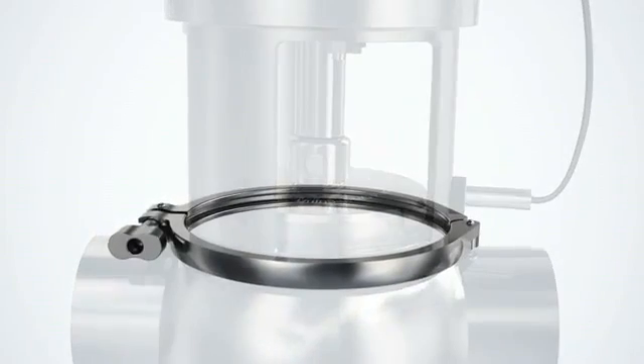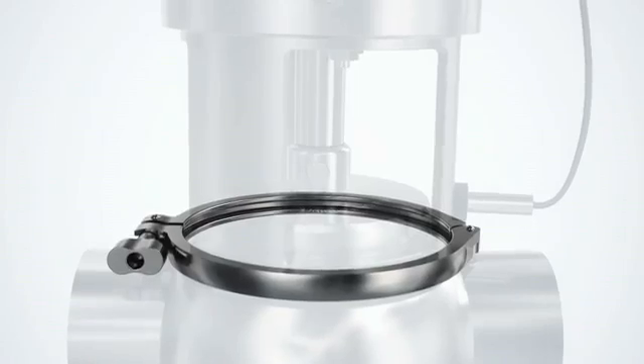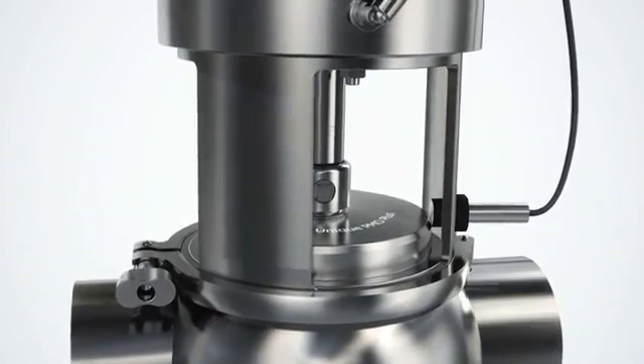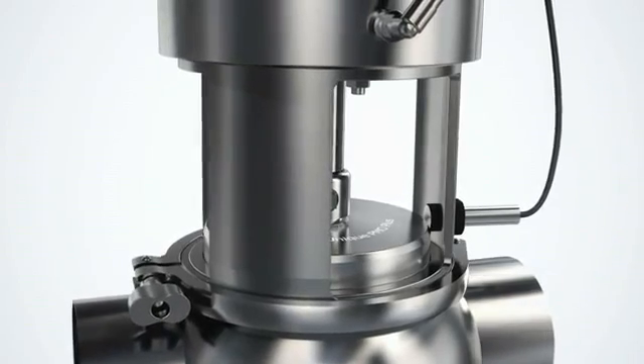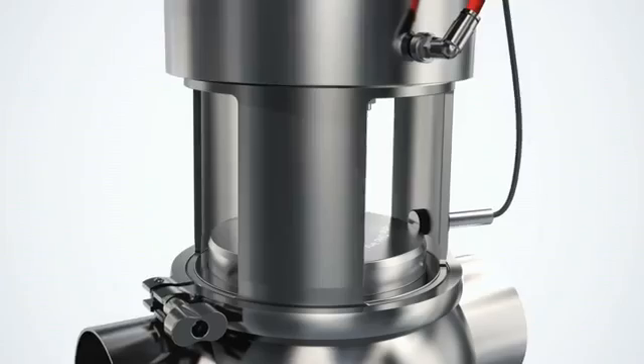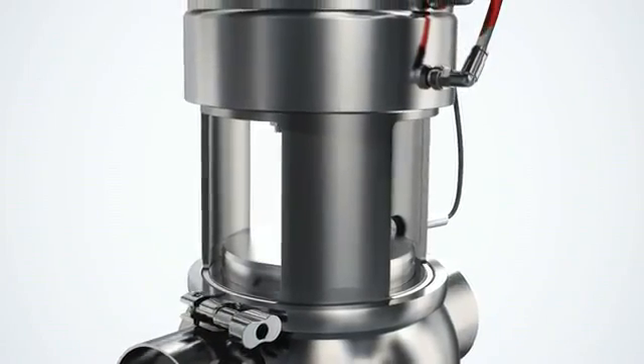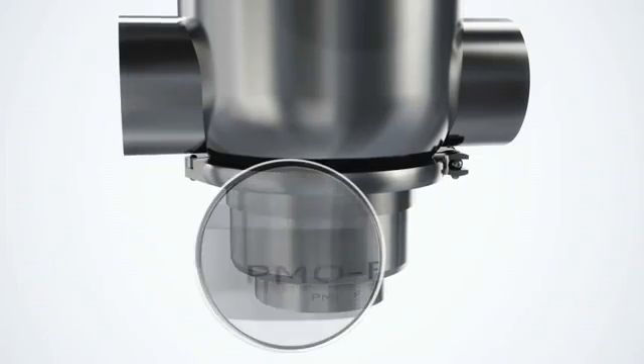The valve body features a top loaded design with clamps for ease of disassembly and reassembly during routine maintenance. The valve body has built in leak detection, defined compression of the static seals and double acting lip seal technology which eliminates the risk of product contamination.